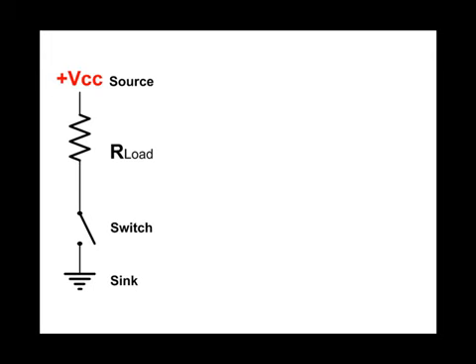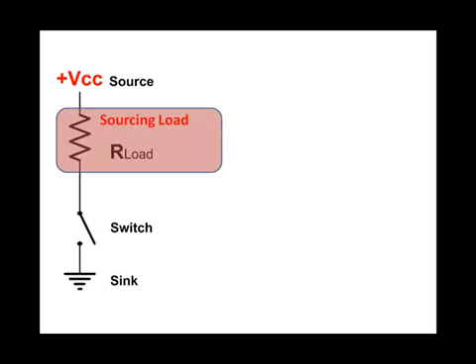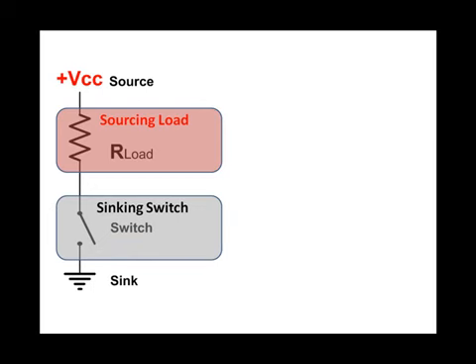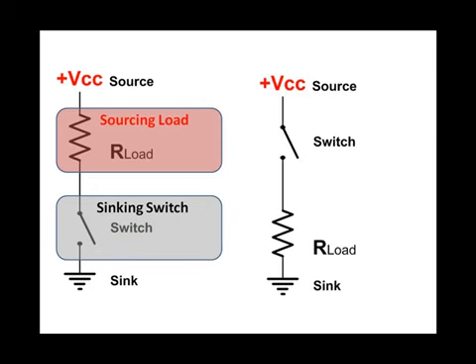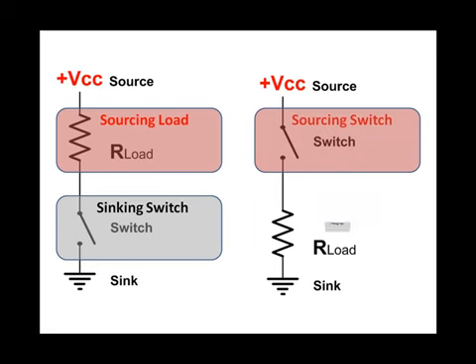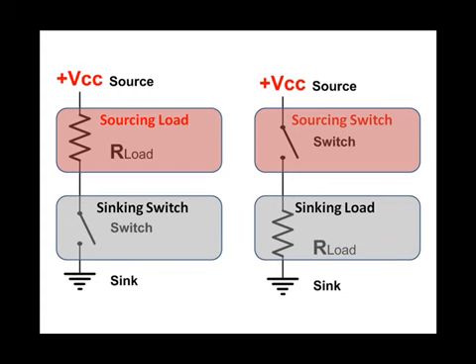If you swap the control switch and the load positions in the circuit, the switch is now sourcing and the load is sinking. Whichever of the two — the control or the load — is closest to the source is the sourcing device; whichever is closest to ground or the sink is the sinking device. Note that the control device in this illustration is a dry switch contact, not a solid-state device such as a transistor, so that same switch can be used in either position as a sourcing or sinking input device.